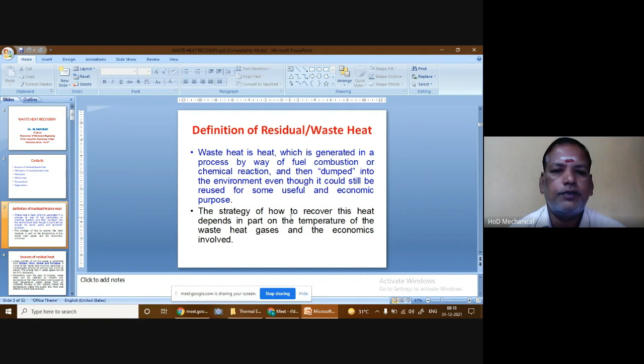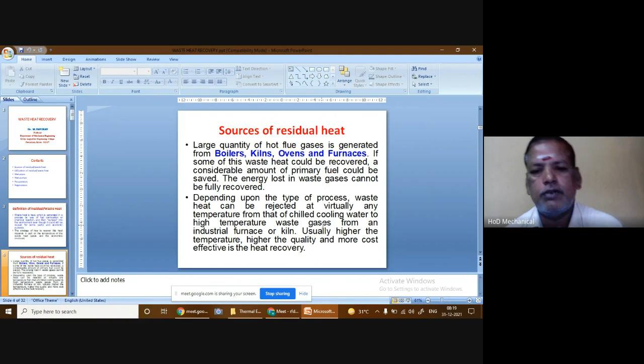Now let us discuss the sources of residual heat. There are many sources. A large quantity of hot flue gases is generated from boilers, kilns, ovens, and furnaces. If some of this waste heat could be recovered, a considerable amount of primary fuel could be saved. The energy lost in waste gases cannot be fully recovered, but to some extent we can recover the heat from the gases. Depending upon the type of process, waste heat can be rejected at virtually any temperature, from that of chilled cooling water to high temperature waste gases from an industrial furnace or kiln. Usually, the higher the temperature, the higher the quality, and the more cost effective is the heat recovery. Depending upon the temperature, we can say how much energy can be recovered.